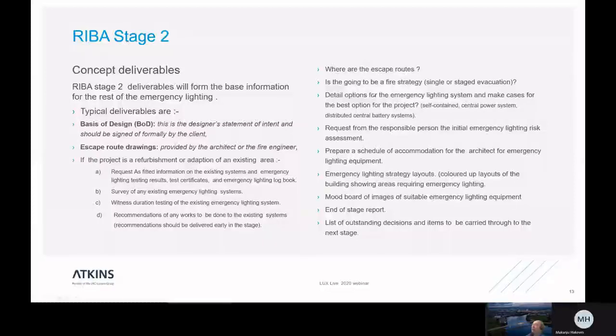Detailed options for emergency lighting systems can make cases for that. So you need to have your early talk with the client to understand what the best option for your project is. And this will depend on the size of the project, the complexity of the project, and the level of size in terms of things, whether you've got space for a power system, a central power system or distributed central battery system. You may not have space for it, so you may have to go self-contained.